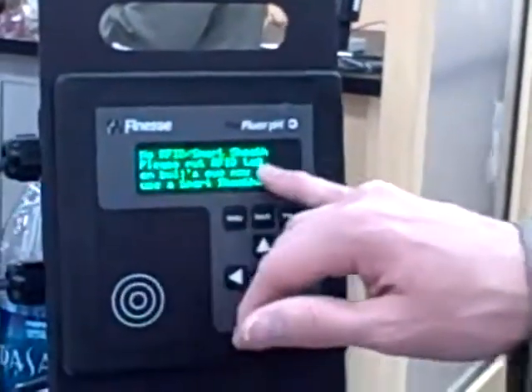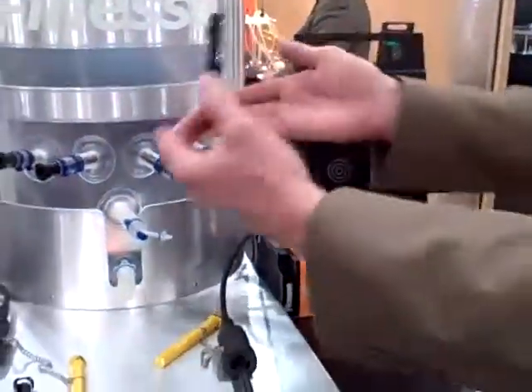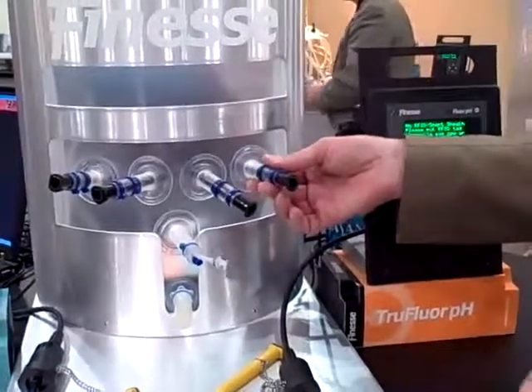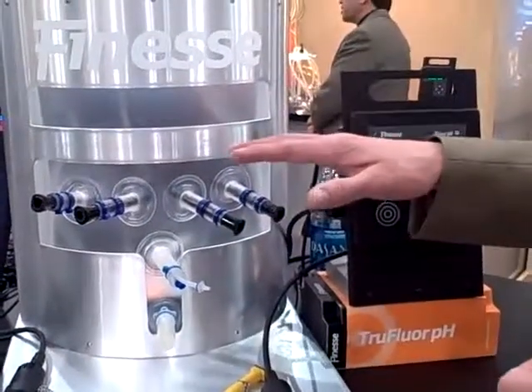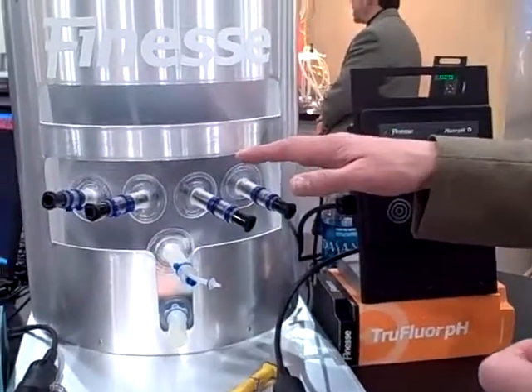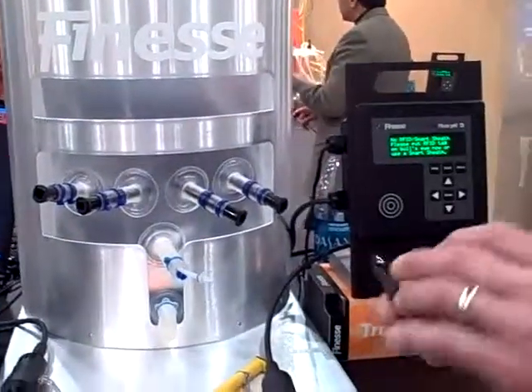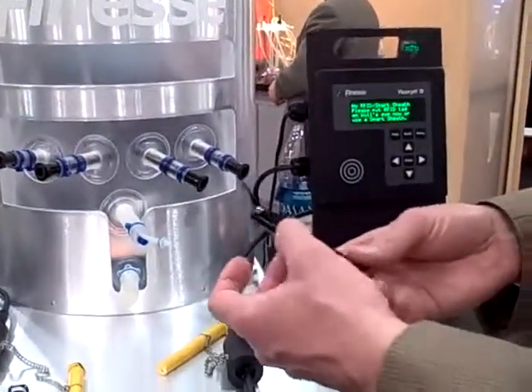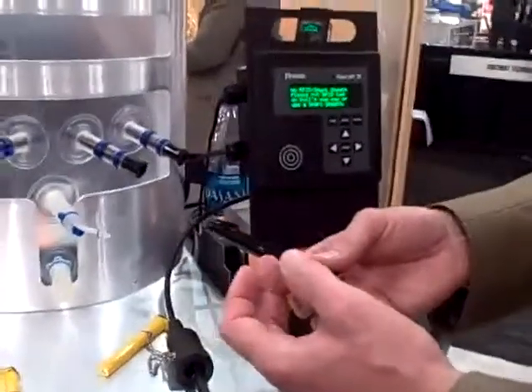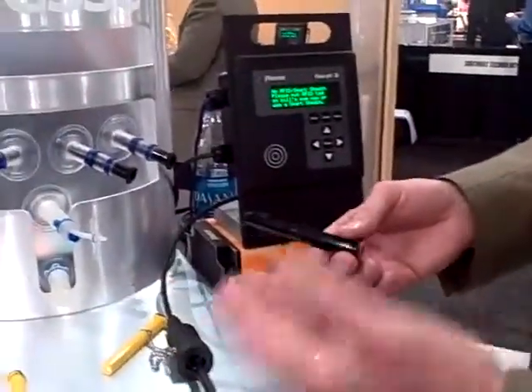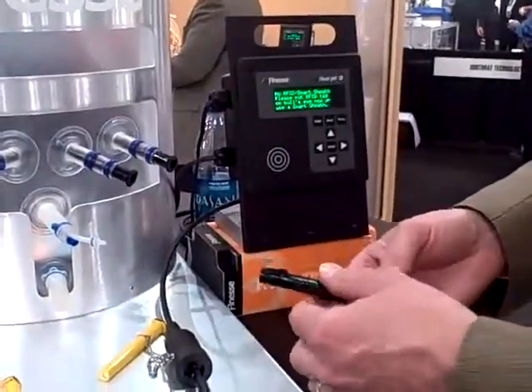The transmitter tells you that there is no smart sheath attached to the reader. The sheath is typically inserted by, in this case, HyClone into their bag. Then it's gamma irradiated to sterilize it, so it's a sterile system. The process media only contacts the outside of this sheath, which is USP Class 6 compliant. It's been tested for leachables and extractables.